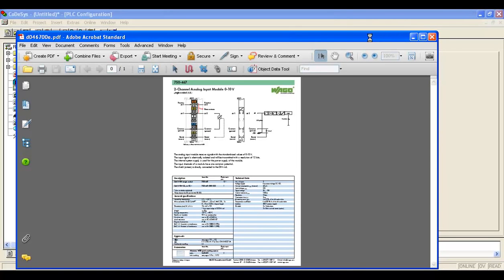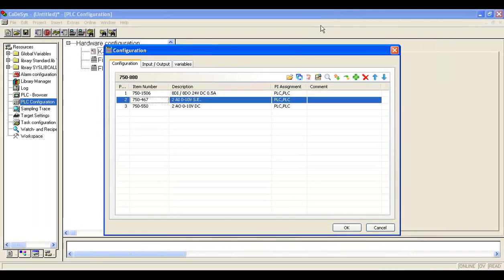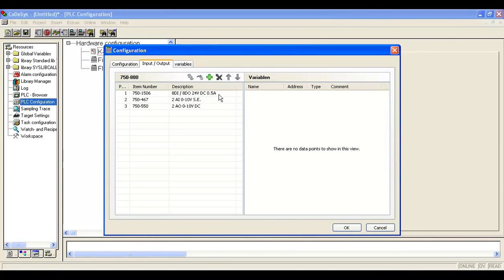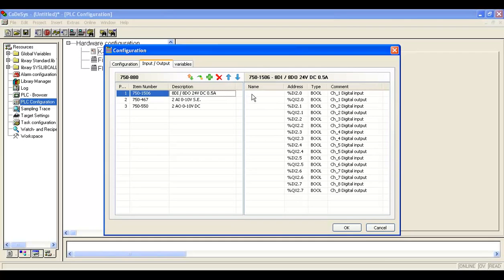Okay. So another thing that you can do, of course, while you're in here is you can point your variable names to the hardware addresses themselves. So in here, I'm just going to put some very simple input and output variable names. You want to be a little careful here when you're using the 8 in, 8 out card, because if you notice, the input-output structure here is alternating. They're not grouped, with inputs and outputs separated from one another. Again, they're alternating. So again, I'm just going to put in a couple variable names here for this project.